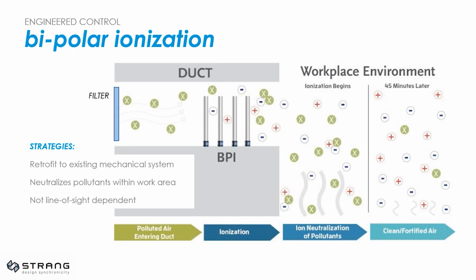The ionized air, when delivered to the occupied space, continues to neutralize viruses within the room, reaching 99% removal after 45 minutes, according to recent test results. Air movement within the occupied space improves the neutralization. Therefore, increased ventilation or ceiling fans can improve the results even further. The neutralized ions that remain are now larger in mass and can be captured by the filters in the return air system. Thus, the process repeats itself throughout the day with each air change.